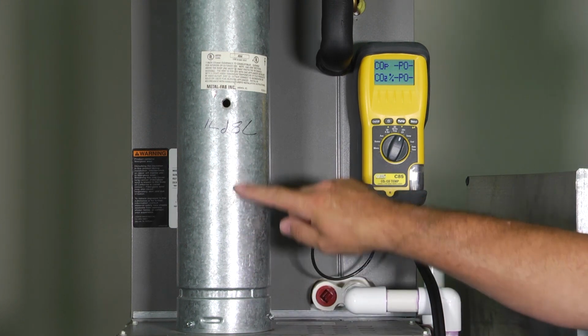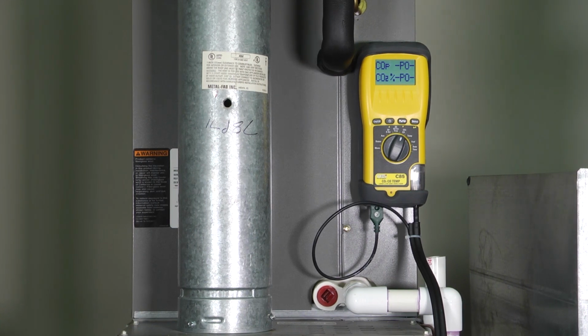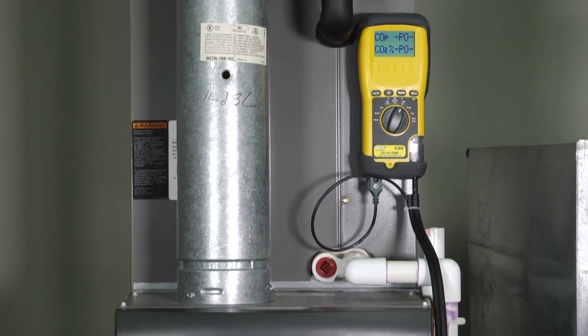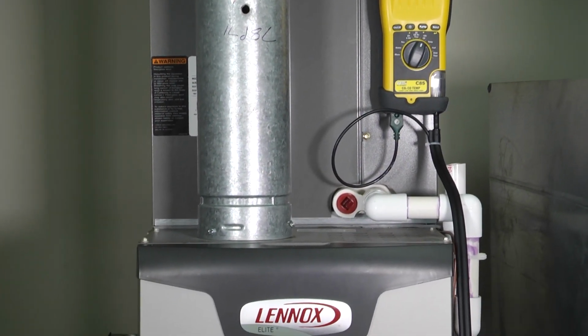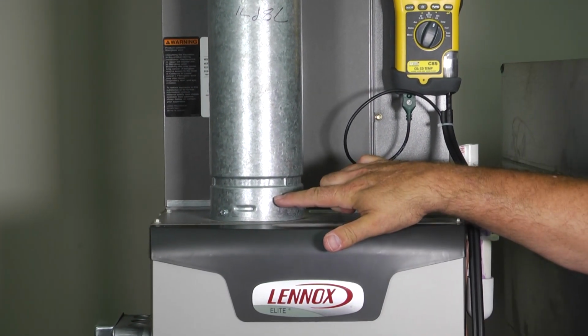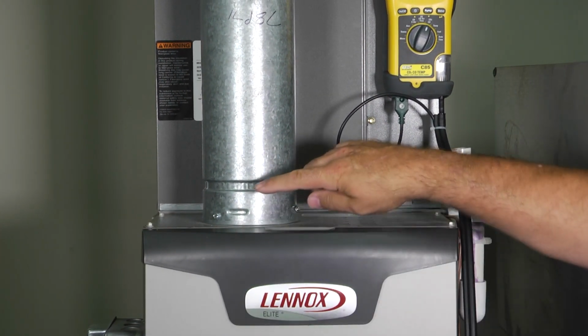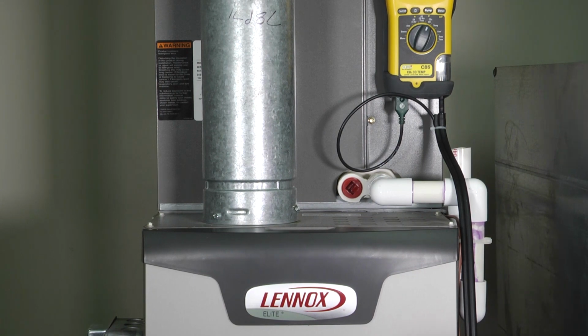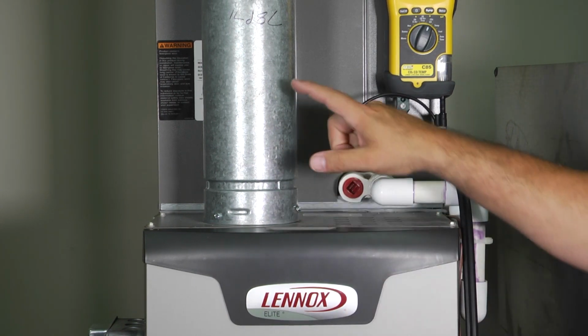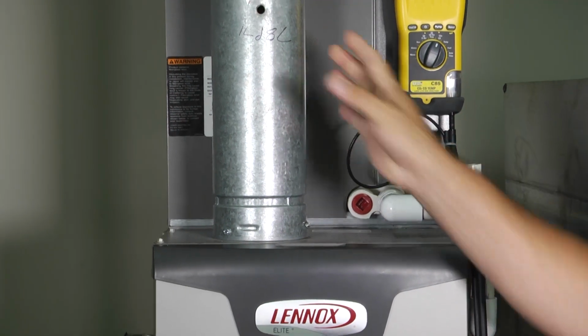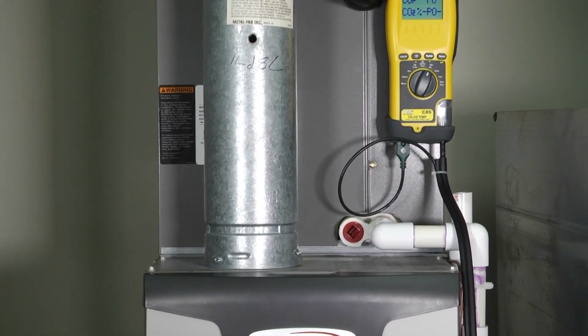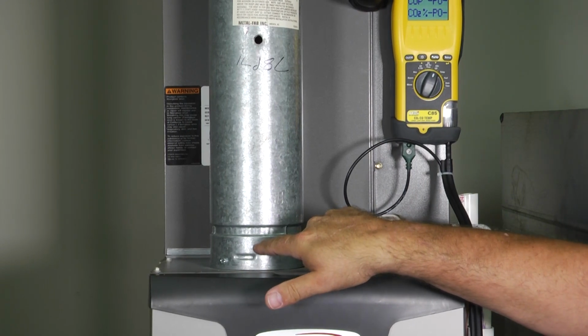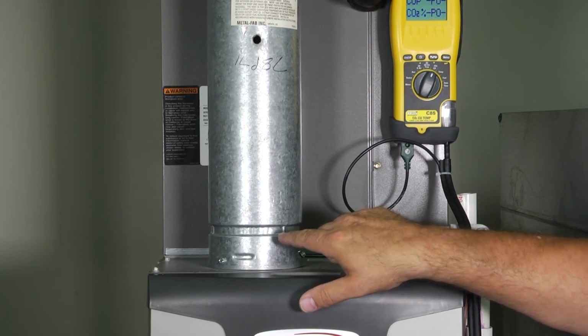Well, in every one of our systems, and again, because this is a lab, we don't have it hooked up, but the first thing we should always have inside our system is what we call a B2C adapter. That's where we've got a small piece of single wall pipe that's connected up to our double wall pipe here, or we call it a draft hood adapter. We're going to put that on there first, then our B-vent, or combustible gas venting, is going to be on there at that point. Now my B2C adapter, or my draft hood adapter, that's where I'm going to drill my hole. In this case, I'm going to be here.